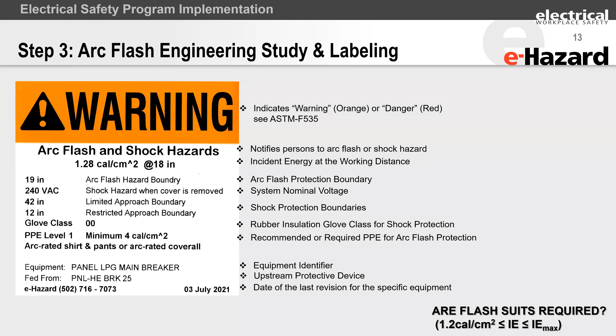And your labels are, as I mentioned previously, going to tell you whether the daily workwear that you procured, the 8 to 12 calorie per square centimeter daily uniform, is adequate or whether you're going to need flash suits as well. Now, in that gap between the maximum calculated incident energy from any piece of equipment and the maximum PPE that you wish to provide, in that range where the PPE you have on site is inadequate for the incident energy available from that piece of equipment, you will not stick an orange warning label, but instead you will use a red danger label. And folks, these are regulated by ANSI Z535. It basically speaks about when do you use a warning label and when do you use a danger label.